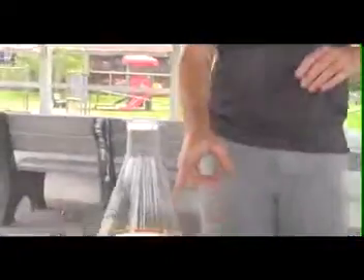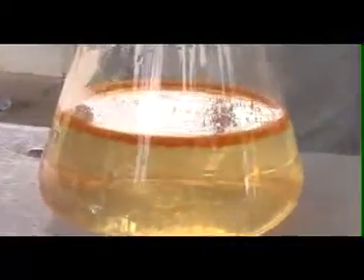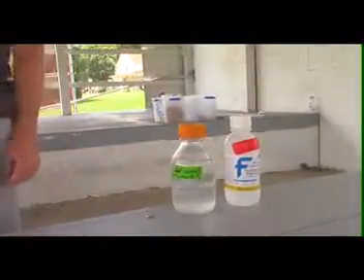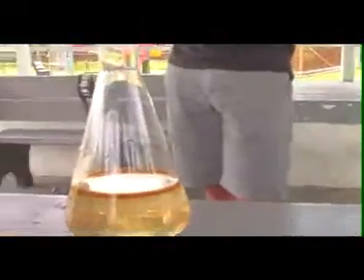We're going to use solar panels to pump the water, and bring it into a water treatment plant. And it's going to go through these steps. It's going to oxidize the water, oxidize the iron, and pull it out. In our plant, the iron will settle to the bottom, and then we'll have clean water on the top. We're going to add an alkali, sodium hydroxide or something like it, to neutralize the water so it will no longer be acidic, and then that water can be released to the stream.